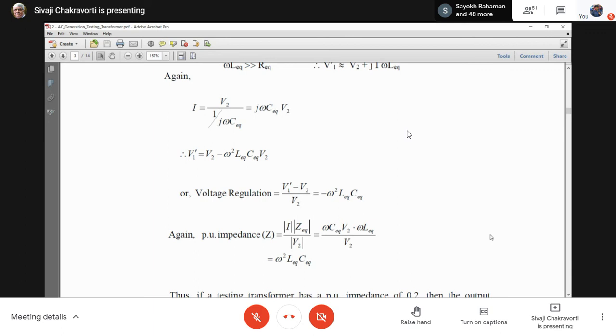But then why is it negative? Where is the capacitive current coming from? The charging capacitances of the transmission line. Correct. The transmission line has a capacitance with respect to ground, which I just cannot avoid. So this capacitance draws a charging current, and that becomes the capacitive current. And the transmission line has its own impedance. So a capacitive current flows through an inductive impedance. There is a negative voltage regulation for such cases, and that is called the Ferranti effect, because Ferranti first found this effect a long time back.